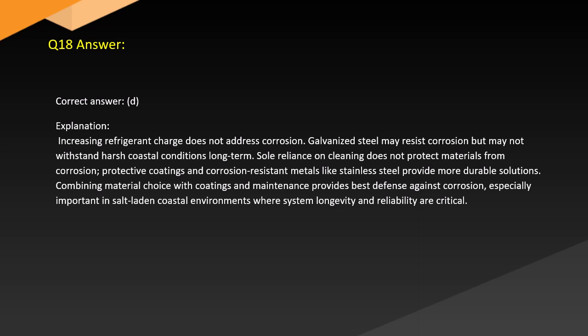Answer. Correct answer: D. Explanation. Increasing refrigerant charge does not address corrosion. Galvanized steel may resist corrosion but may not withstand harsh coastal conditions long term. Sole reliance on cleaning does not protect materials from corrosion. Protective coatings and corrosion-resistant metals like stainless steel provide more durable solutions. Combining material choice with coatings and maintenance provides the best defense against corrosion, especially important in salt-laden coastal environments where system longevity and reliability are critical.